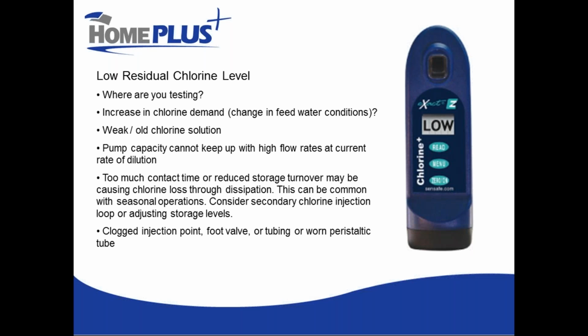Certainly look for things like clogged injection points, foot valves, clogged tubing, and worn peristaltic tubes. If you have a peristaltic feed pump, you'll know what those tubes are. Those tubes get squished and they wear out over time. So they are a wear and tear item.